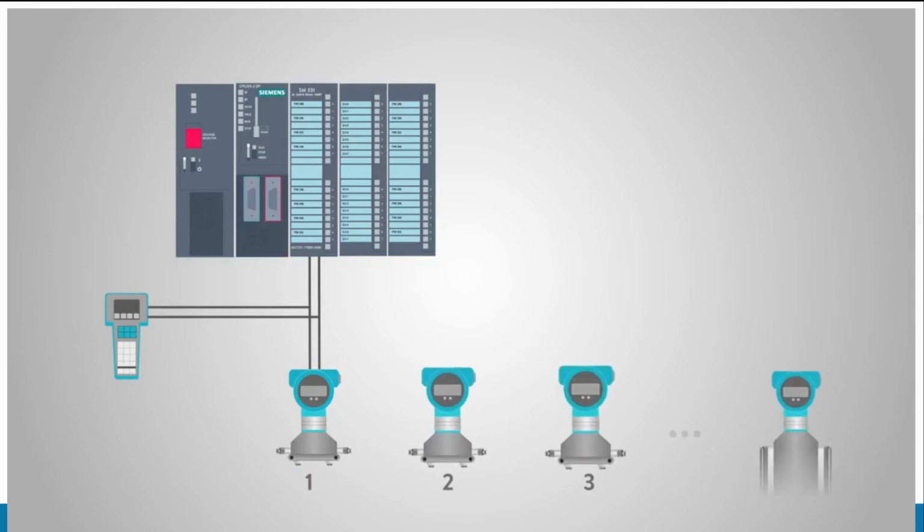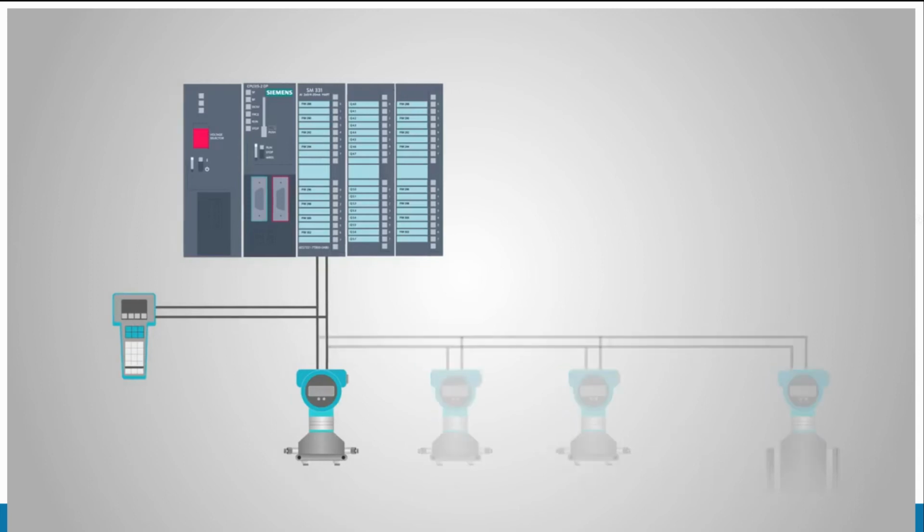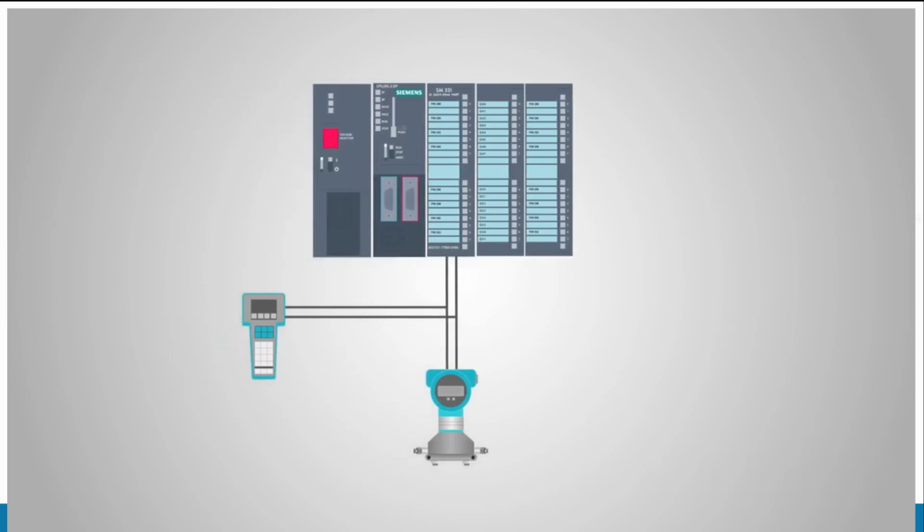Networking Hart devices in most control systems applications is not practiced, because of its limited speed and its cumbersome multi-drop network topology. We generally assign only one node or sensor to each Hart signal loop. Fortunately, Hart allows for multiple master nodes, so that the control system and a handheld communicator can both be connected to the loop and can communicate with the device at the same time.